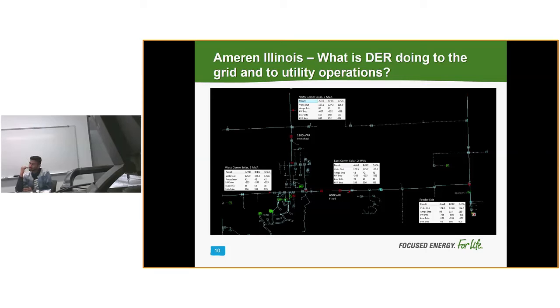Voltage regulators typically don't help. You could think of using them, but they don't respond quickly to voltage change, especially with cloud coverage moving over a solar farm that keeps spiking the voltage up and down. They can't react fast enough - they need a few minutes before the logic kicks in and they start tapping up or down. So voltage regulators can't react fast enough to cloud coverage moving in milliseconds, maybe seconds.